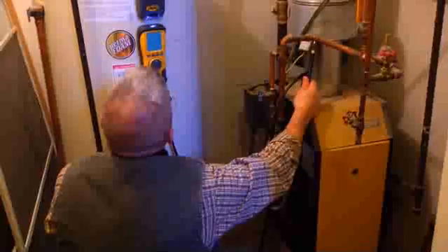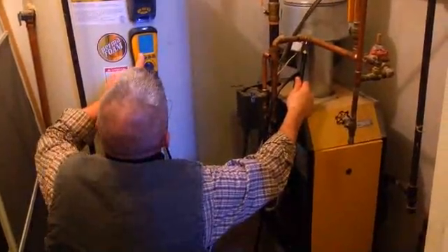Next, Jim tests the furnace and water heater for their efficiency and checks their ventilation for carbon monoxide. We set up the house to perform as it could, not necessarily that it would, during the winter by shutting doors, blocking airflow, and turning on all vents or dryers that vent air to the outside, so that we can depressurize the house to see if it can change the pressure enough in this space to cause the system to backdraft. And if it's close and we were to go and tighten up the home, we could actually cause a major CO poisoning. We don't want to do that. You have to look at the house as a system to make sure that any of the measures you employ are going to still preserve the health and safety of the homeowners.